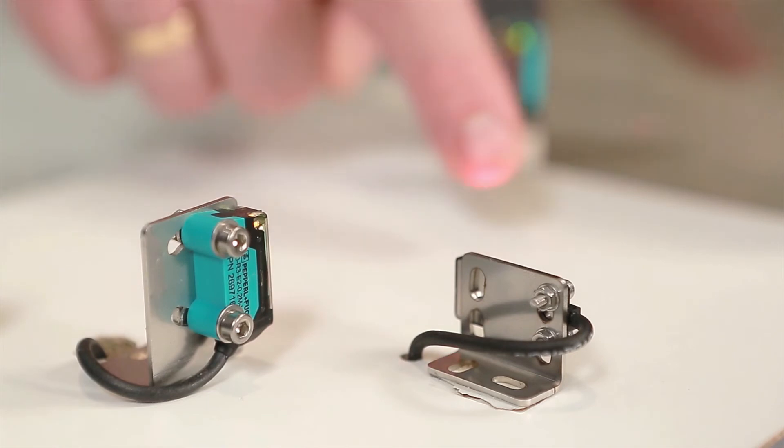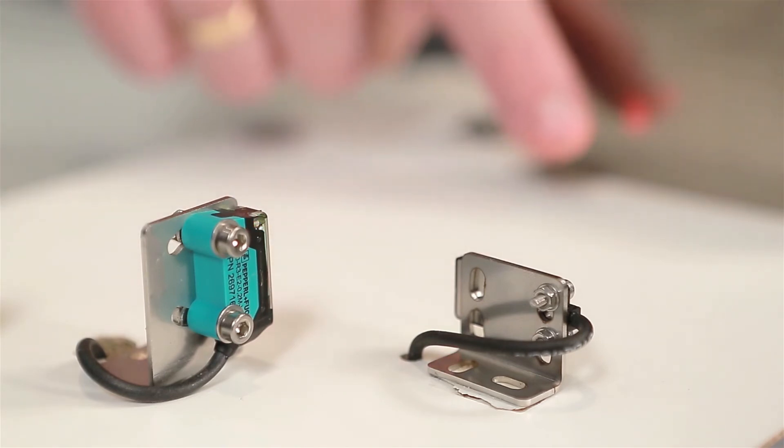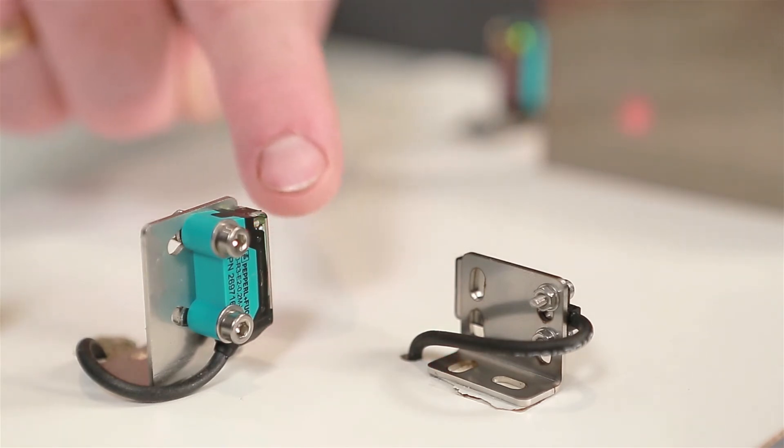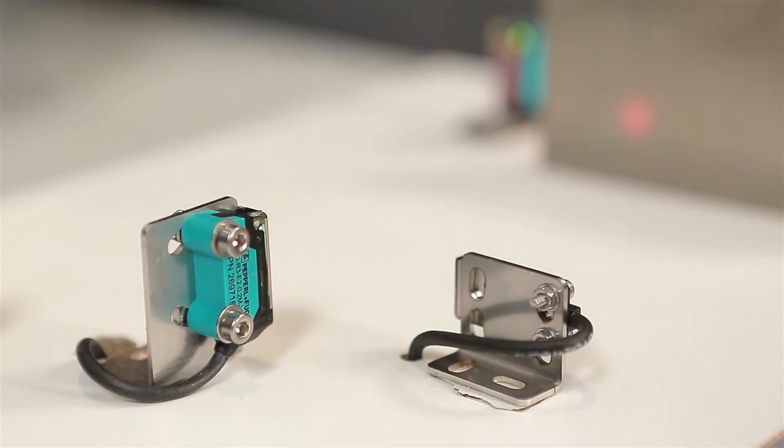You can choose either LED sensors or laser sensors, which are available in this housing design for the first time. Both products are diffuse mode sensors with background suppression. They are based on the triangulation principle. The light from the emitter is reflected by the diffusely reflecting object and caught by the photoelectric receiver.